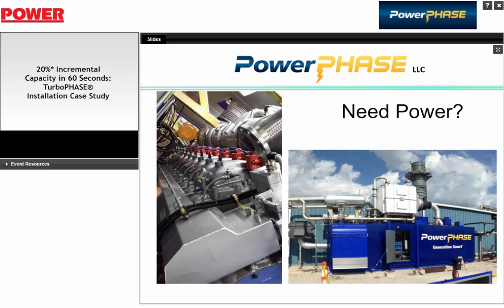Okay. What is the effect on combustion dynamics for both diffusive and DLN combustion systems? Okay, so you heard a little bit about my bio. We've built pretty much all the popular frame combustors in my previous company, Power Systems Manufacturing, so I'm half a combustion expert. And so you can maybe believe me when I tell you that actually when we add more air to the combustor, we're actually improving every element of what you would look for in combustion stability, which in turn is dynamics. So on a really hot day, the combustor's really off design and really is looking for more fuel and more air.